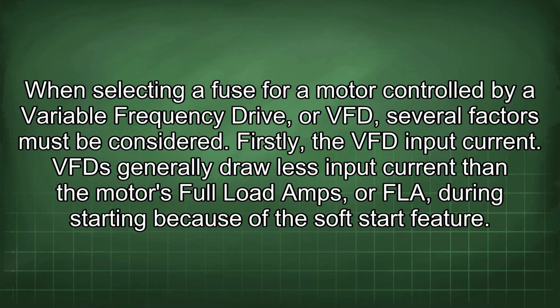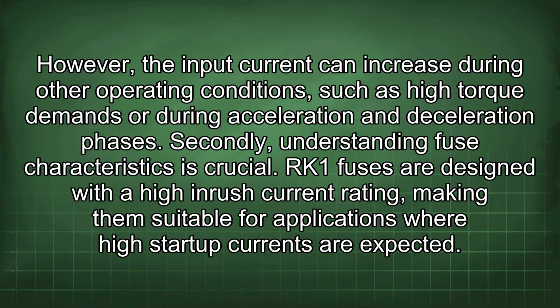When selecting a fuse for a motor controlled by a variable frequency drive, or VFD, several factors must be considered. Firstly, the VFD input current. VFDs generally draw less input current than the motor's full load amps, or FLA, during starting because of the soft start feature. However, the input current can increase during other operating conditions, such as high torque demands or during acceleration and deceleration phases. Secondly, understanding fuse characteristics is crucial.